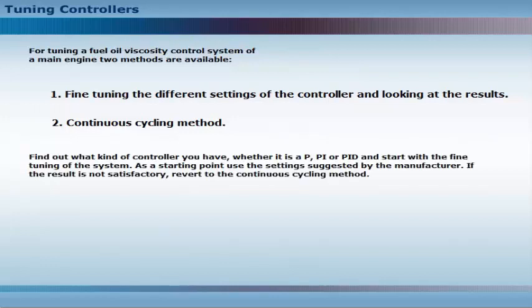Find out what kind of controller you have, whether it is a P, PI, or PID, and start with the fine-tuning of the system. As a starting point, use the settings suggested by the manufacturer. If the result is not satisfactory, revert to the continuous cycling method.